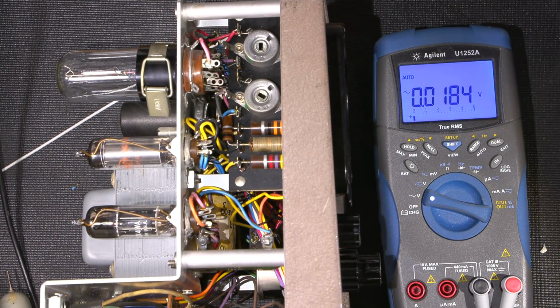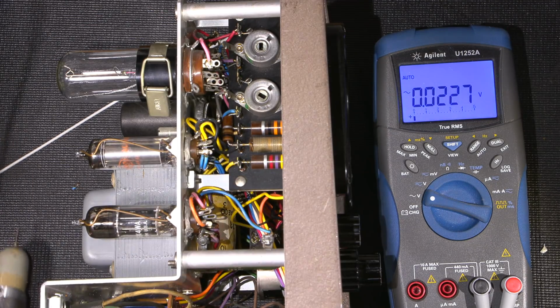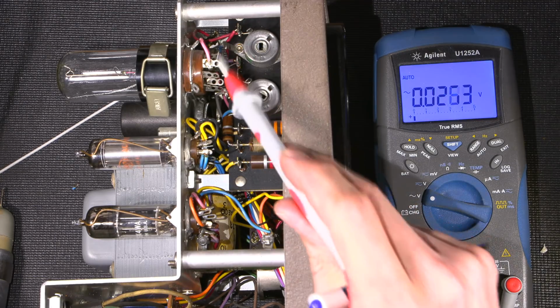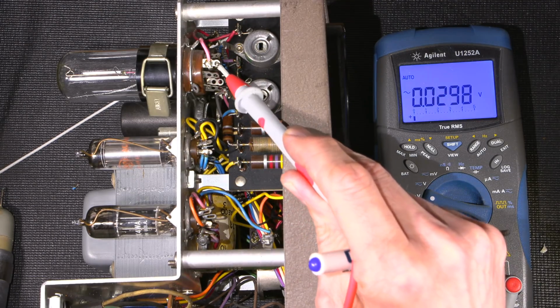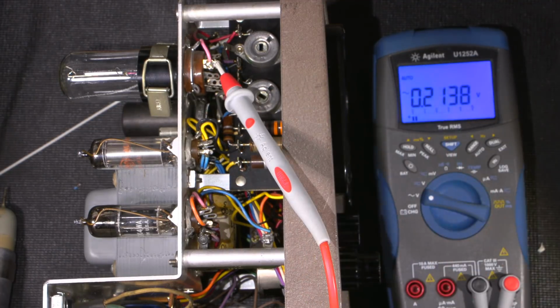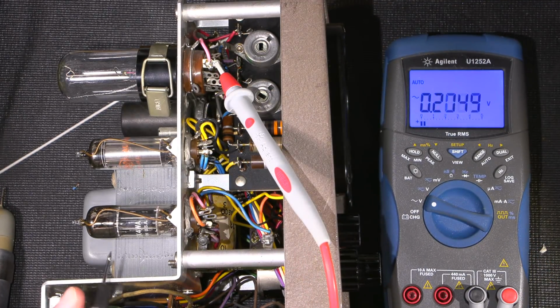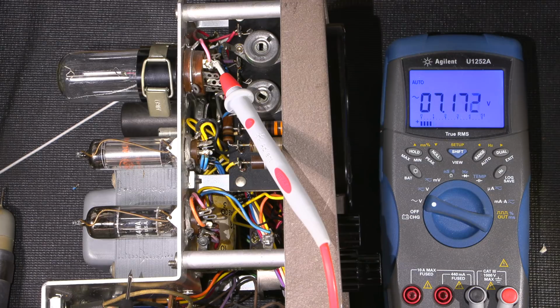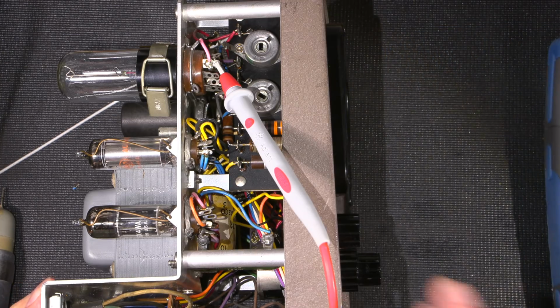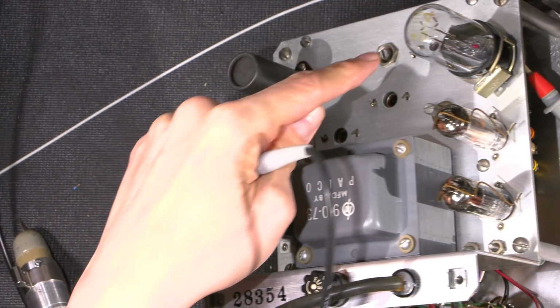The first thing I'm going to do before I start the alignment is set the filament voltage of the tube in the probe. So that's a very important thing to check. It's very easy to do. So this pink wire here runs to the tube. We'll put our AC voltmeter on there, and I can just touch the chassis and get an idea. That's 7 volts, so that's pretty high. It's supposed to be at 6.3. So the adjustment point is right there.